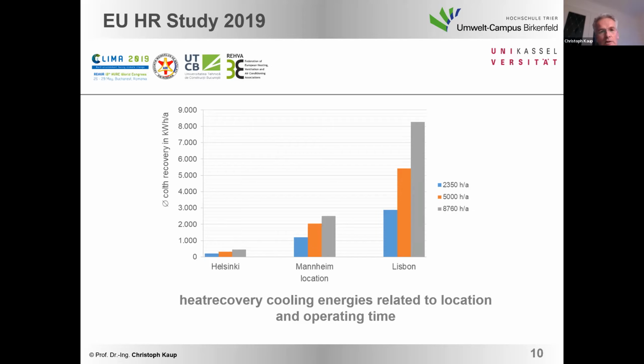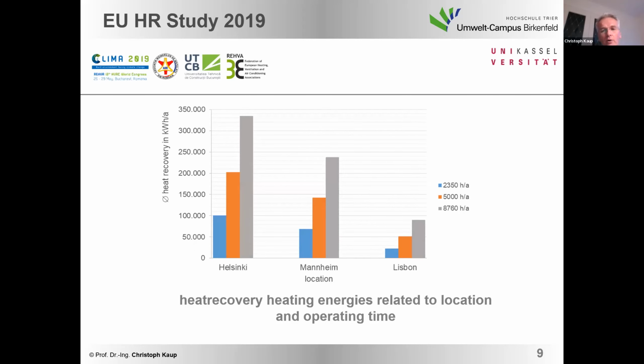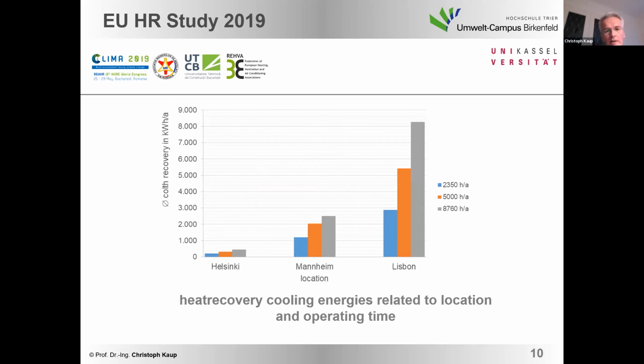But you see in a hospital in Lisbon, for example, we have a possibility to recover cold in a range of 8,000 kilowatt hours. And if we look at the winter period, we see we have in the winter 80,000 kilowatt hours per year in the same location and the same operating time here in Lisbon. So it's even a factor of 10 more relevant in the winter period than the summer period. And in Helsinki, cooling loads are more or less negligible with regard to the heat recovery.